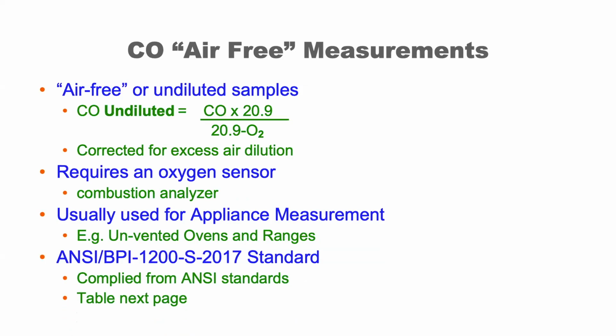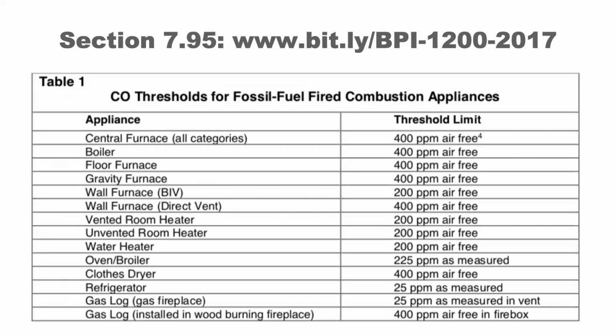If you're familiar with BPI, the Building Performance Institute, their standard BPI 1200, released in 2017, has a table of CO air-free measurements for various types of equipment that comes from the ANSI standard. We'll show that in just a second. And here you go. This comes from the BPI 1200 standard. If you want to go to that link at the top, type it in exactly as you see it, bit.ly/BPI-1200-2017. You'll find table 1 in section 7.95 that tells you what the limit is.